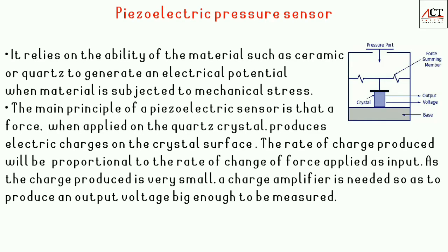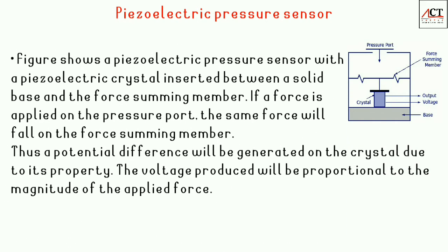The next is the piezoelectric pressure sensor. It uses piezoelectric material like quartz or ceramic, which has the ability to generate electric potential whenever it is subjected to mechanical stress. So, whenever a force is applied on the quartz crystal through a force summing membrane which distributes the applied pressure equally on its surface, it produces charge. And the rate of charge produced is proportional to the rate of change of force applied.